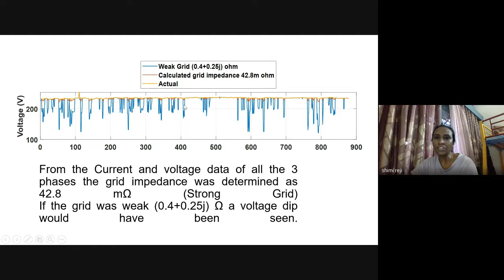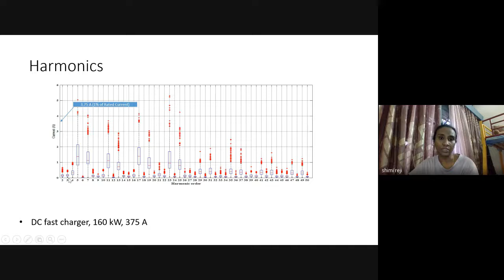The harmonic profile for all 94 charging cycles was taken, and it was found that the 5th, 7th, 11th, 17th, and 23rd harmonics were high, more than 1% of the rated value. Even the 4th harmonic was high. So we were interested in knowing why this even harmonic was high, whether there is any imbalance in this circuit, which had to be analyzed. These things were studied.